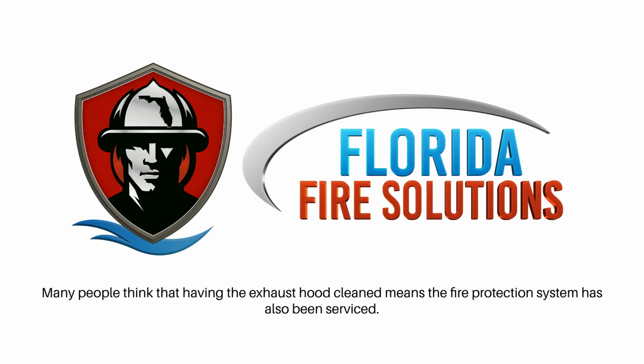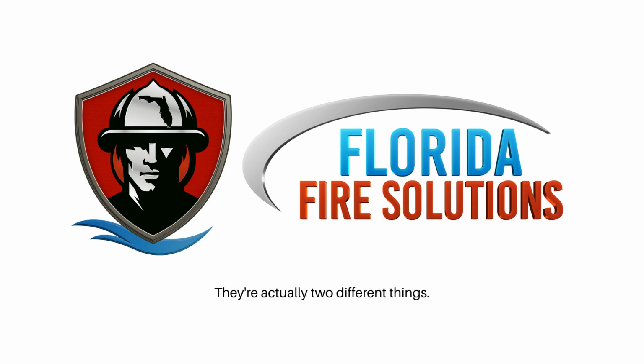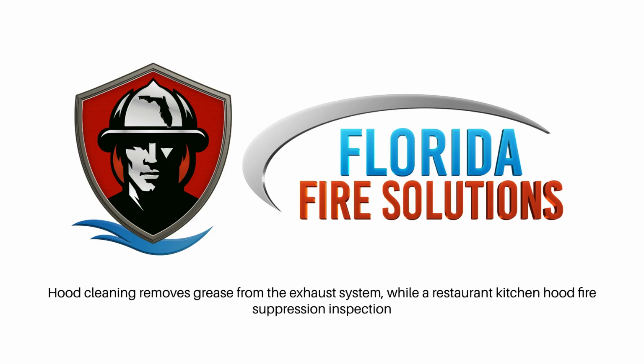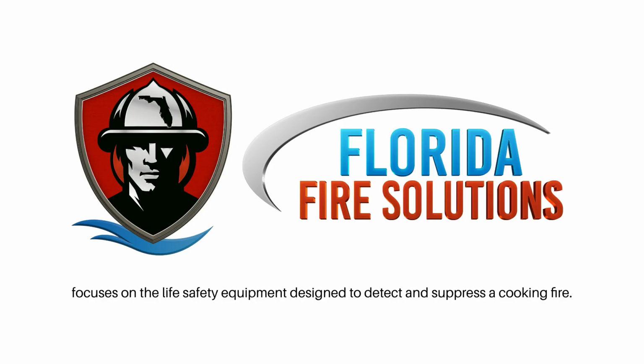Many people think that having the exhaust hood cleaned means the fire protection system has also been serviced. They're actually two different things. Hood cleaning removes grease from the exhaust system, while a restaurant kitchen hood fire suppression inspection focuses on the life safety equipment designed to detect and suppress a cooking fire. Both services are important, but they serve different purposes.